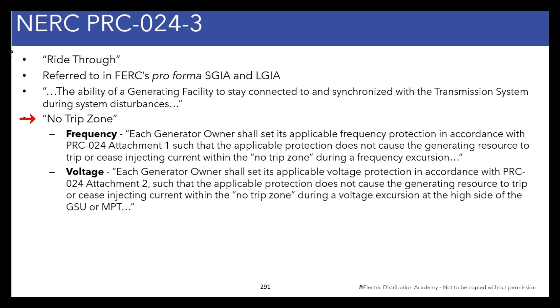The standard defines a no-trip zone, one for frequency and one for voltage. The important phrase is: does not cause the generating resource to trip or cease injecting current. With inverters, they can not only trip offline, but they can also enter a condition known as momentary cessation, where the inverter is still connected to the system but ceases injecting any current. If the generating facility enters the no-trip zone with respect to frequency, it must stay online.